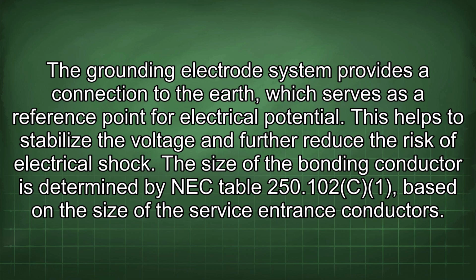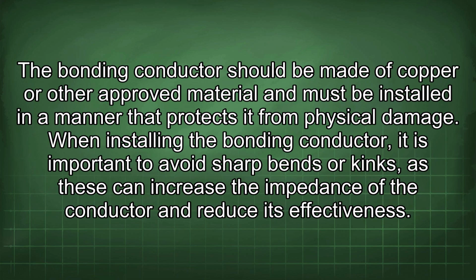The size of the bonding conductor is determined by NEC Table 250.102(C)(1), based on the size of the service entrance conductors. The bonding conductor should be made of copper or other approved material and must be installed in a manner that protects it from physical damage. When installing the bonding conductor, it is important to avoid sharp bends or kinks, as these can increase the impedance of the conductor and reduce its effectiveness.